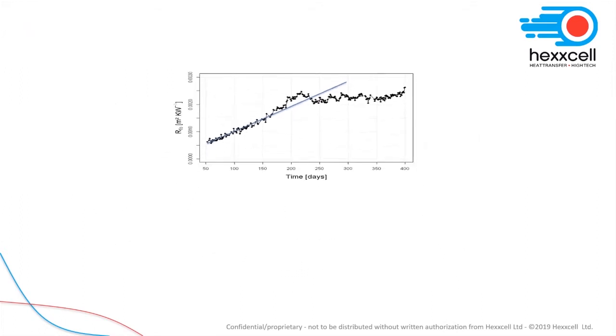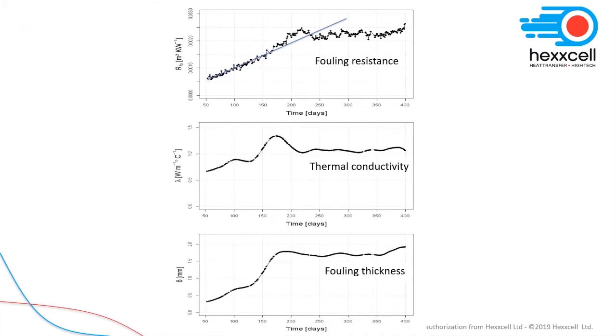However, let me show you how the fouling resistance can be very misleading and how it only represents part of the picture. For this particular heat exchanger, we were able to calculate the thickness of the fouling layer as well as its thermal conductivity, shown below the fouling resistance. The results of this analysis show that actually the problem in the heat exchanger was generated way before the time shown by the fouling resistance itself.